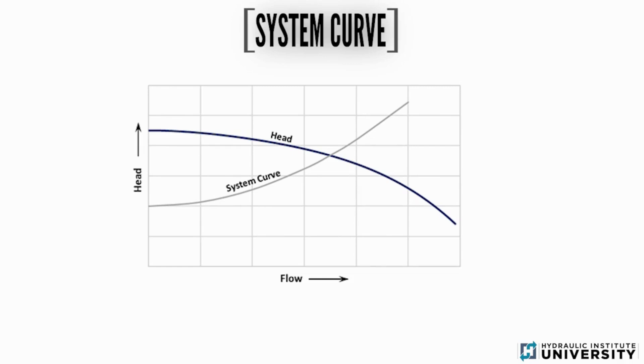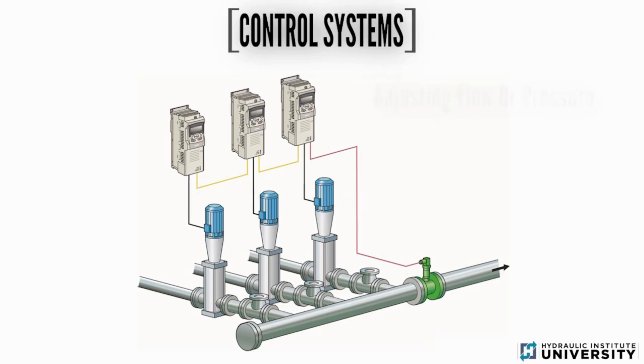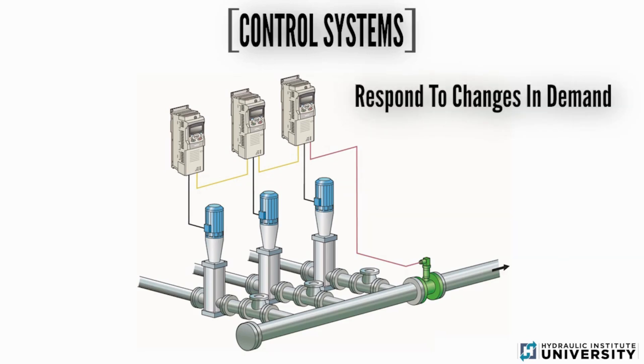By overlaying the pump curve, the operating flow and head is identified at the intersection point, which is discussed in more detail in the introduction to basic operating theory training module. Adjusting a system flow rate or pressure is a consideration for most pumping systems to respond to changing demands and conditions.